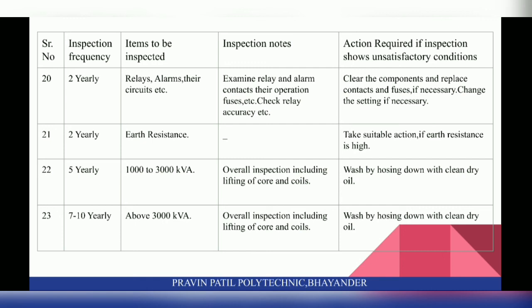On a five-yearly basis for transformers of 1000 to 3000 KVA, perform an overall inspection including lifting of the core and coils, and wash by hosing down with clean dry oil. For transformers above 3000 KVA, this overall inspection is done on a seven to ten yearly basis. In both cases, all parts of the transformer must be thoroughly inspected.